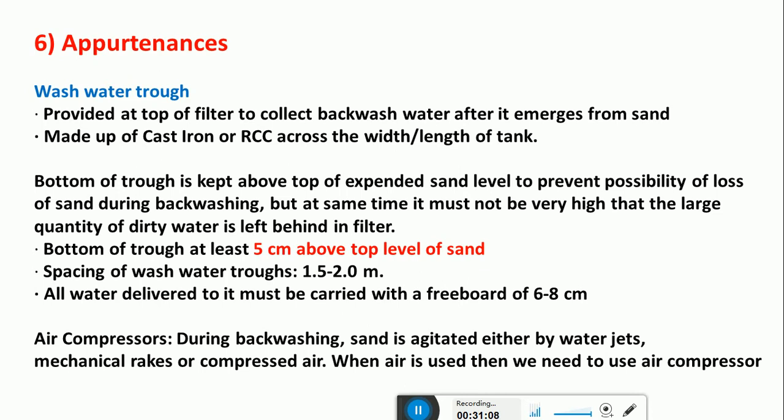Okay, so to clean the sand in the case of rapid sand filters, instead of removing the top layer of the sand, we do a process called the backwashing process. Wherein water with high pressure is injected through the under drainage system to the bed of gravel and sand to remove the clogged impurities. To collect the impure water, canals are provided at the top, which collect the wash water in the wash water troughs, and that water is taken out, and again the filter will be put into operation.